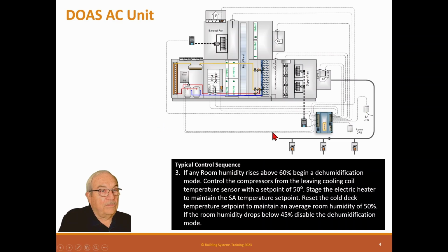So basically we're taking this coil and dropping the temperature down, wringing the moisture out, then reheating the air back up to be the temperature they want for the inlet air. And of course we're using the heat wheel to capture all of that as we can here. And the refrigerant circuit is actually inputting that here. Now you'll notice that this is also going to have an enthalpy control. And let's go look at it.